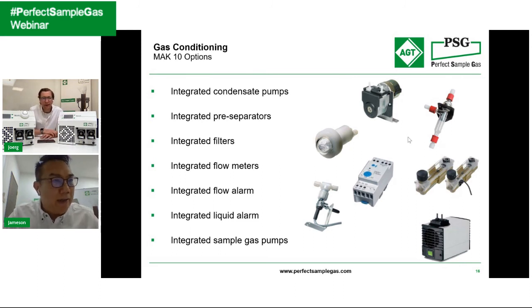You asked how to clean the exchanger. I'd like to say it depends on the model, whether it's from another supplier or from us - it depends on the model. We can just remove the exchanger from the top and wash it. Another option, if you don't want to do that, is to use phosphoric acid: you reverse the peristaltic pump. The tubing of the peristaltic pump is supposed to pump out, but if you reverse it, you're actually pushing the phosphoric acid back into the exchanger and pushing out all the contaminants. This is one way of washing the exchanger.